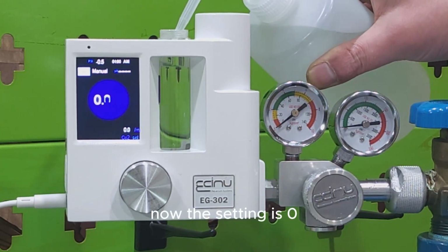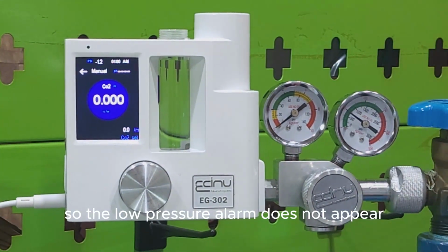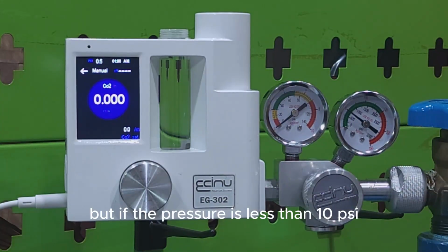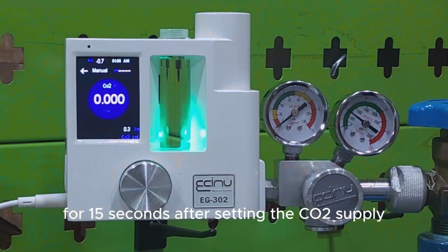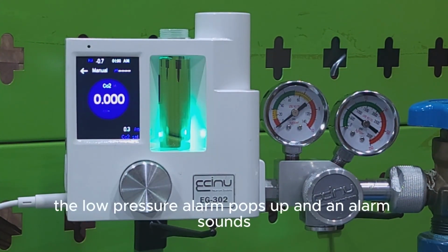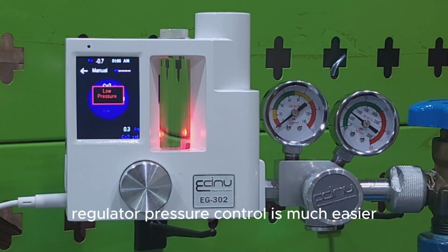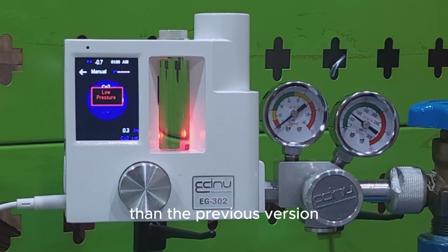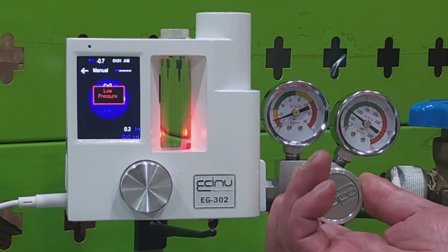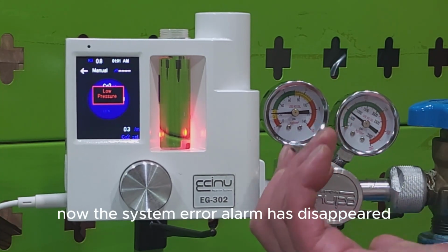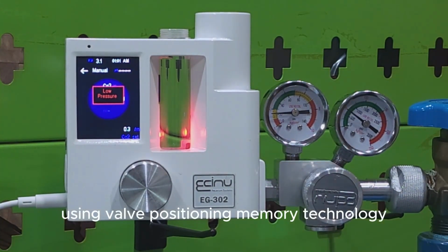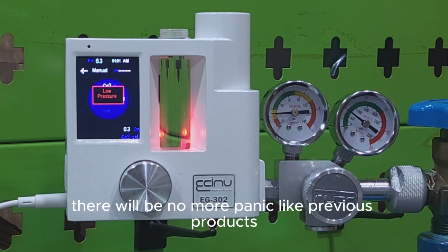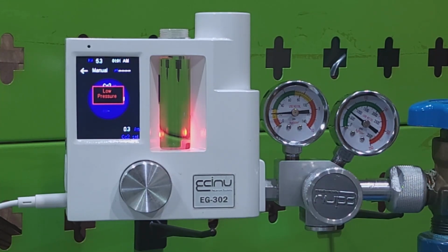Now the setting is 0, so the low pressure alarm does not appear. But if the pressure is less than 10 psi for 15 seconds after setting the CO2 supply, the low pressure alarm pops up and an alarm sounds. Regulator pressure control is much easier than the previous version. Now the system error alarm has disappeared. Using valve positioning memory technology, there will be no more panic like previous products. You are now ready to use.